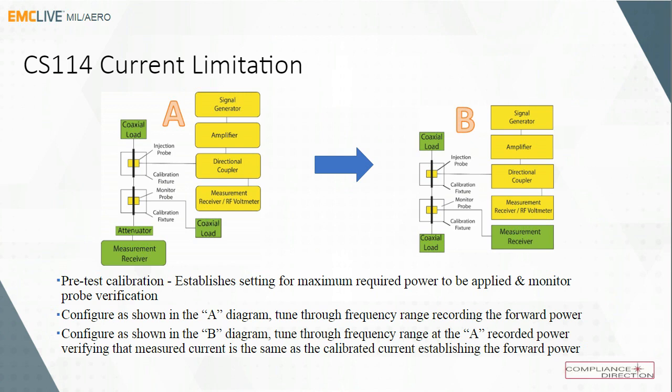We note also that there's a monitor probe here that just simply comes over to a coaxial load. That came into being with revision G to allow us to do a thorough calibration check of the monitor probe. Now, that assumes that this monitor probe we're using here gets its full check out, so when we use it for other systems, this thing is checked out.